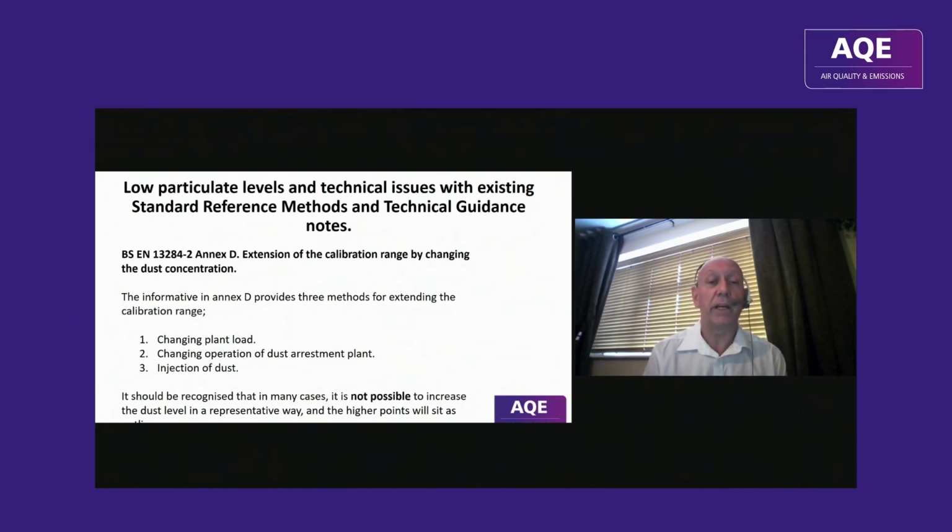And quite often, and we've tried this in the past, the higher points will often sit as outliers in the assessment and cannot be used. So the standard does give allowance for methods to try and achieve a valid calibration range, but in reality, it is still very difficult to achieve, and you often end up with just a low-level cluster.